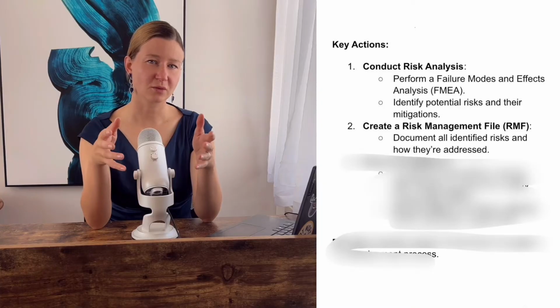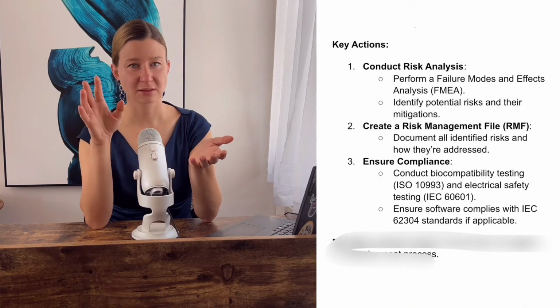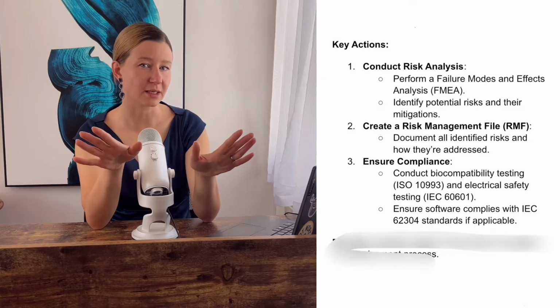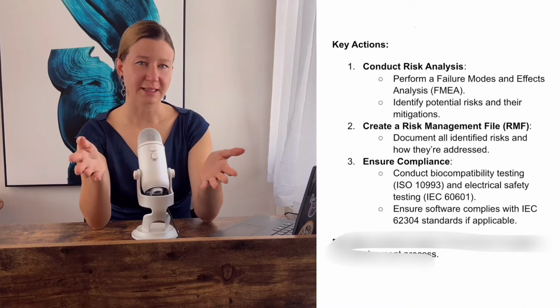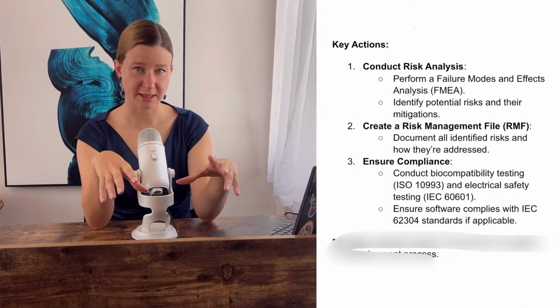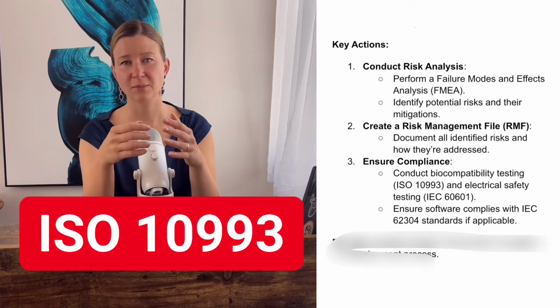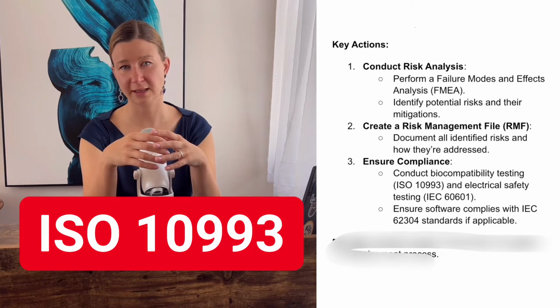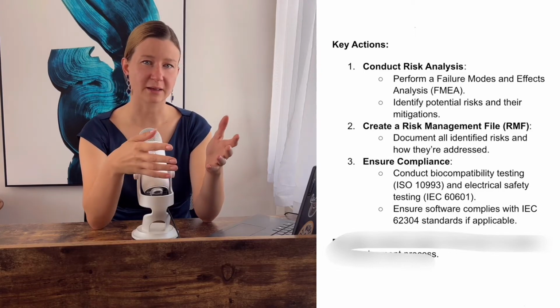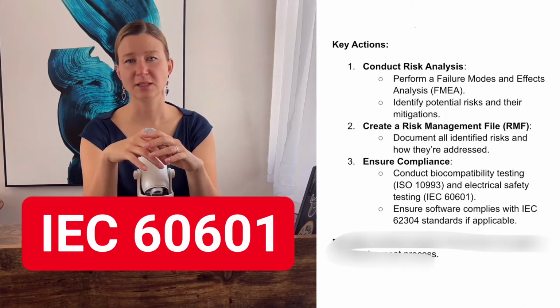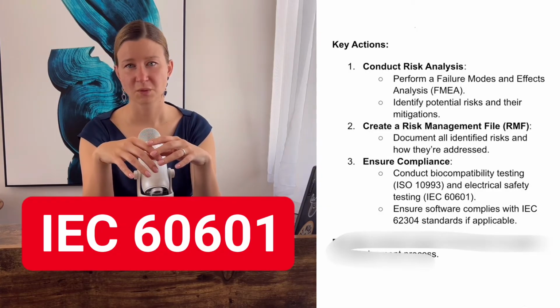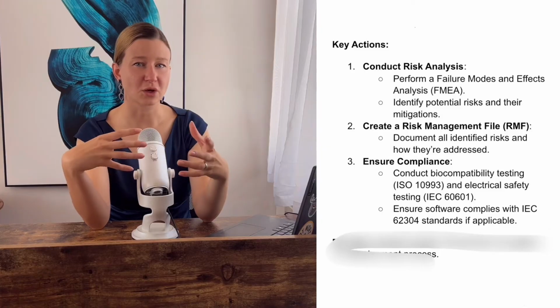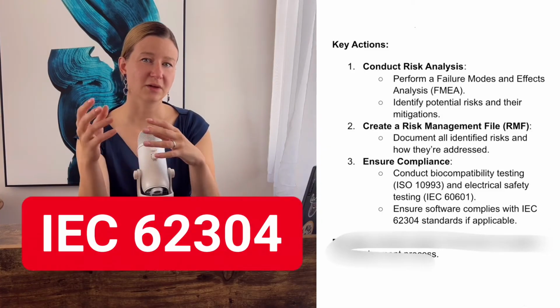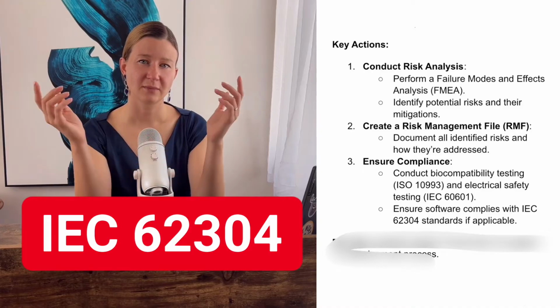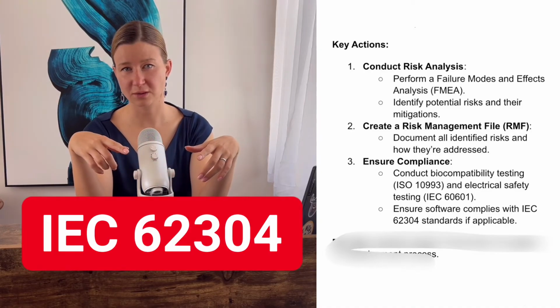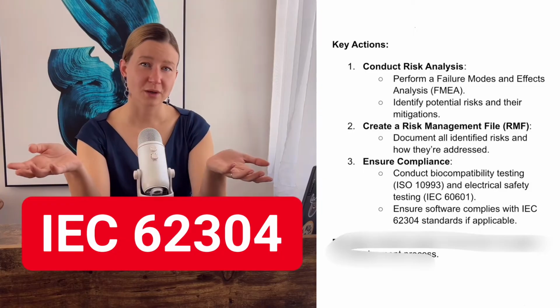Now let's talk about meeting the rules, or compliance. If your device touches the human body, like a skin patch, you'll need to do biocompatibility testing to make sure all the materials are safe. There is a standard for this testing. It's called ISO 10993. If your device uses electricity, like a heart monitor or a pump, it has to meet another standard, 60601, to prove it won't cause any electrical shocks or malfunction. And if there is software in your device, it needs to follow IEC 62304 rules to show that it's built safely. Unfortunately, those tests aren't optional.